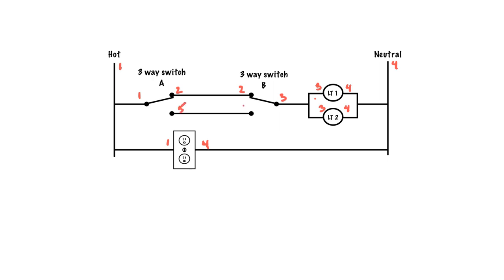We have up here a five and a five. So just to walk through again: a one here goes to this node, that's a one going to this side of the receptacle. A two here goes straight across — there's a switch break, so then we go to three. Three is attached to this as well as to this. Then we have the lights in the way — four, four. And we finish up with five, five. It doesn't matter which way you number it, as long as at the end you end up with five wires in total.